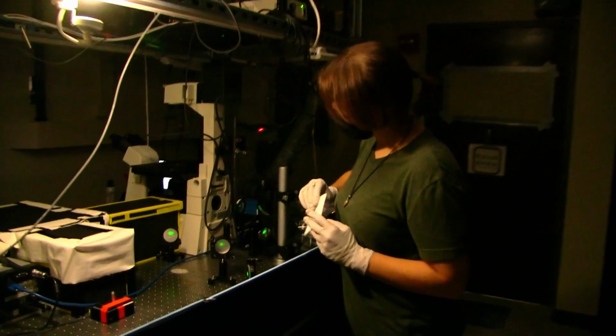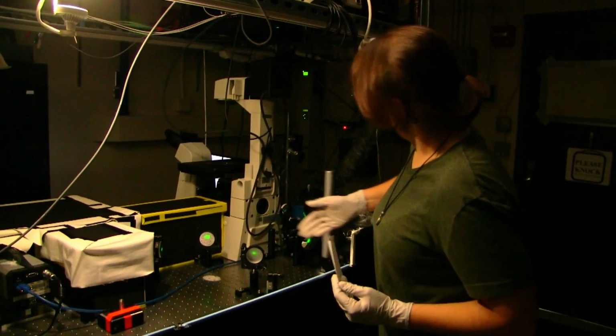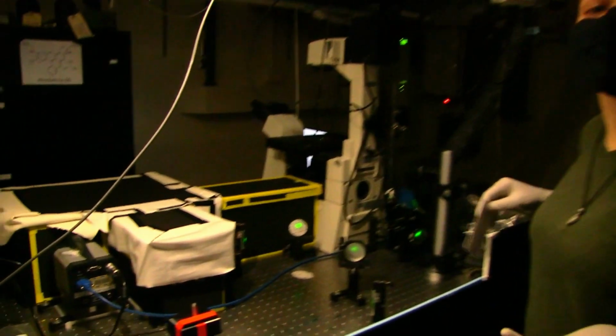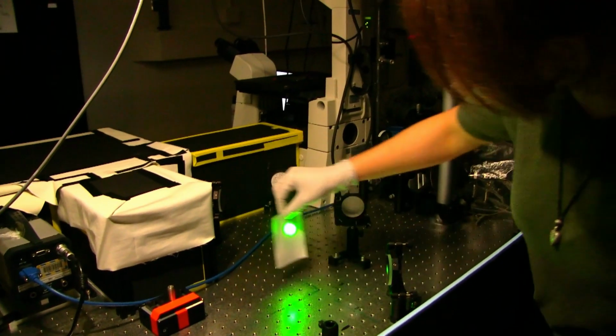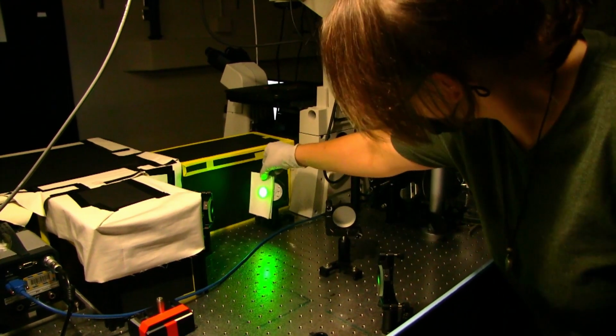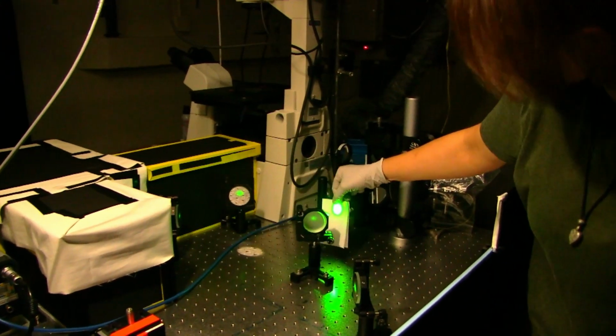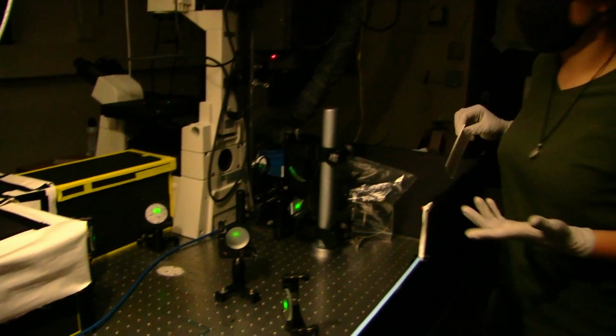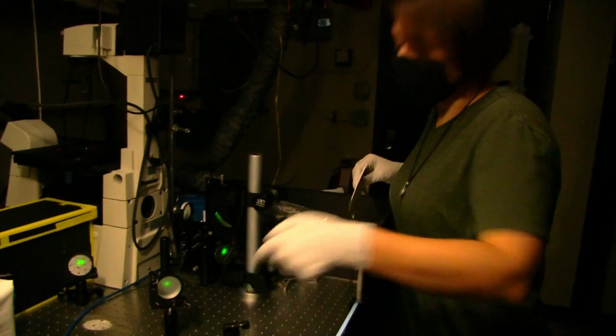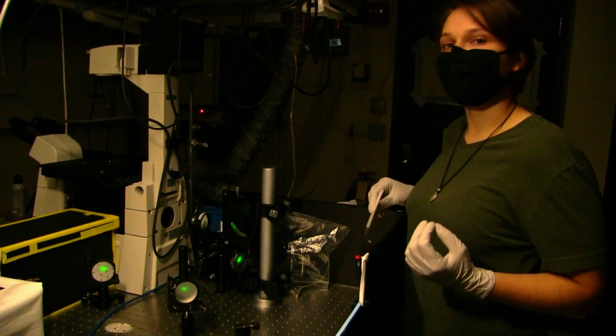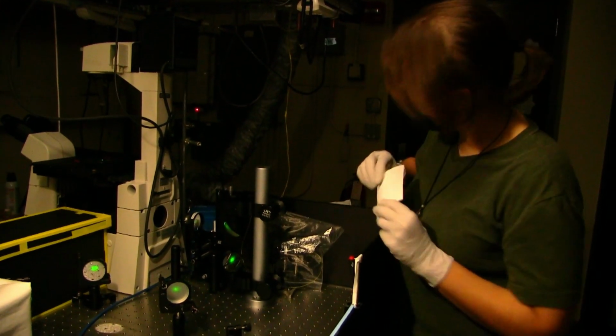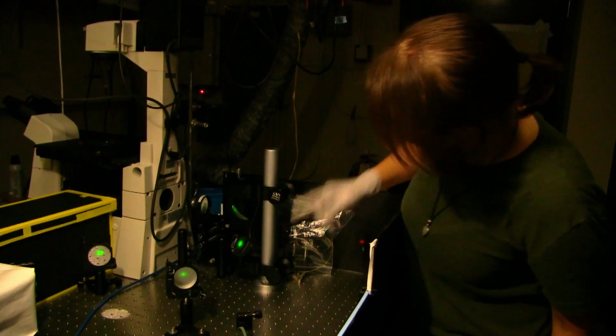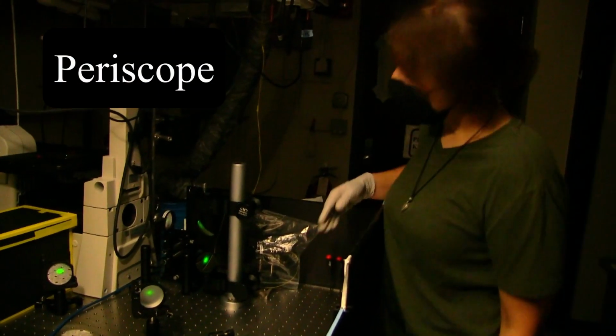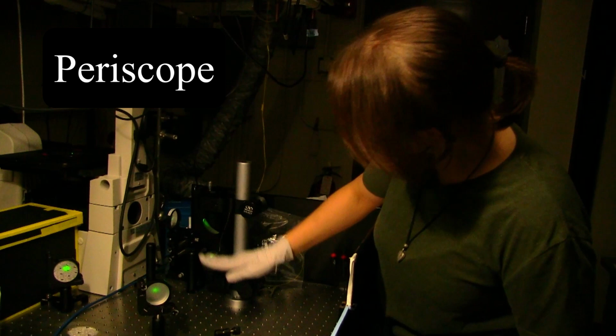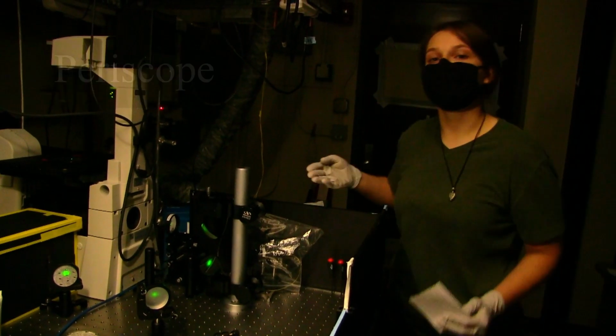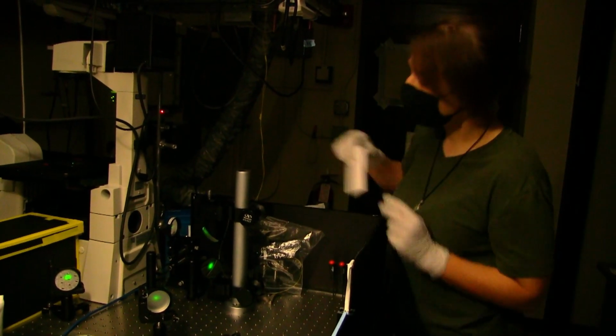Now that our beam's all the way over here, it's going to hit a series of mirrors. Mirrors are just like the ones you might have in your bathroom at home. And they're going to bounce our beam back and forth, again, bringing it where we want it to go. These little knobs inside the mirrors also give us very precise control over where exactly our beam is placed. This set of mirrors here, these two, form a periscope, which is going to raise our beam from this level to this level. That's the height we need it to be to get into the back of our microscope.